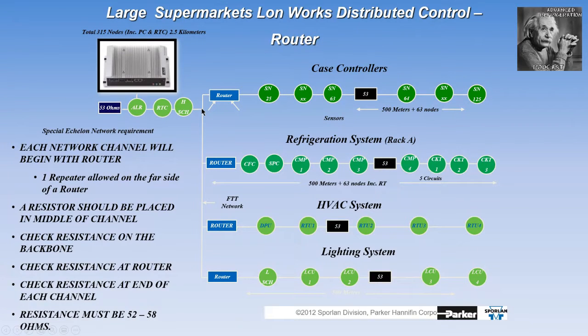Here's the star right here, and then we have channel A, case controllers, and we can have multiple channels. Channel B, we can have a channel for rack A, rack B, rack C. Here's another channel for the HVAC system, and here's another for lighting. So you can have multiple channels - 4, 10, 12, 16, however many you want. Again, we don't want any more than 60 to 64 simple nodes, or no more than 50 compound nodes.